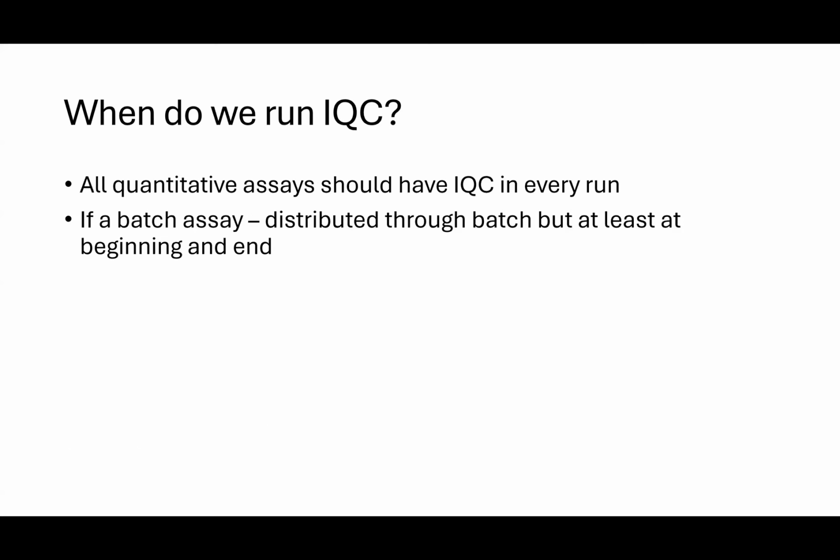The next part that we need to think about when we have a QC is when should we be running it? And this is kind of a difficult question to answer in a single slide or in a few minutes. The first thing to say is that all quantitative assays should have an IQC in every run, and a minimum of 2 levels of IQC should be run once on the day of performing the test.